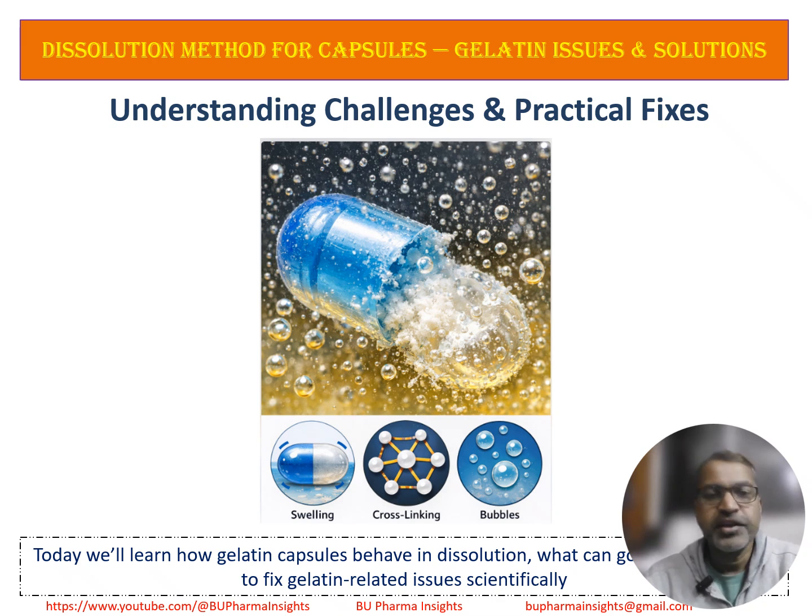Hi everyone. In this video, we'll discuss dissolution method for capsules, gelatin issue and solutions. Capsule, especially gelatin capsules, behave very differently from tablets, and many dissolution failures actually come from the capsule shell, not the drug itself. Common issues include shell cross-linking, sticking to the vessel, floating, incomplete or delayed release.